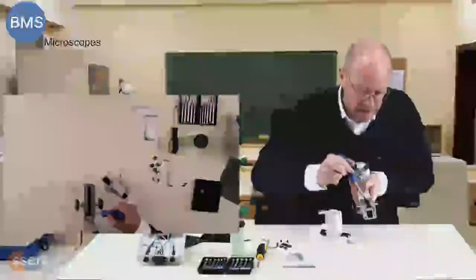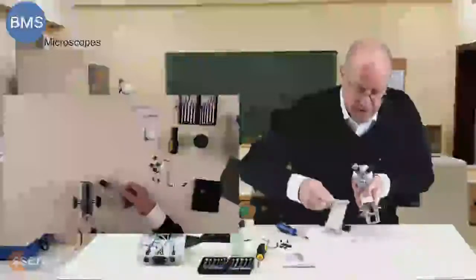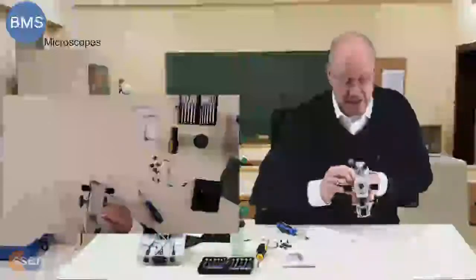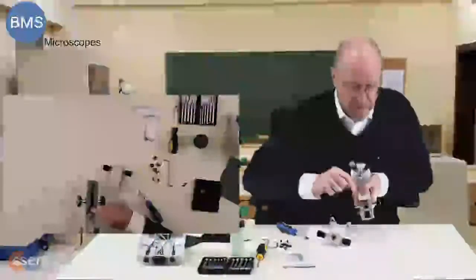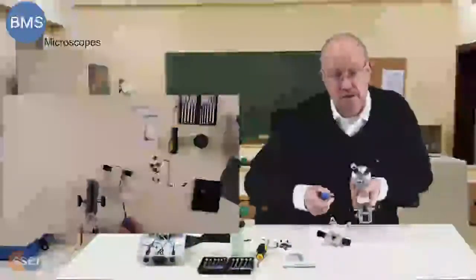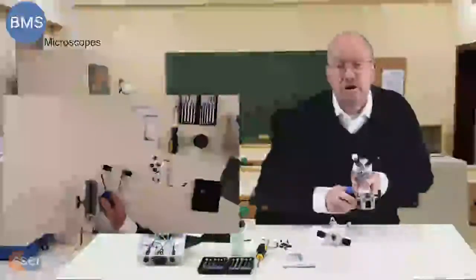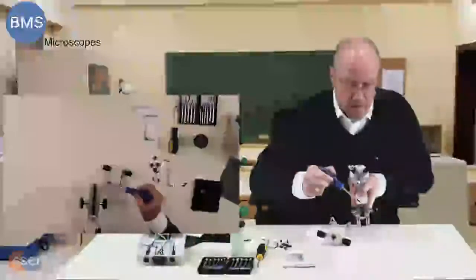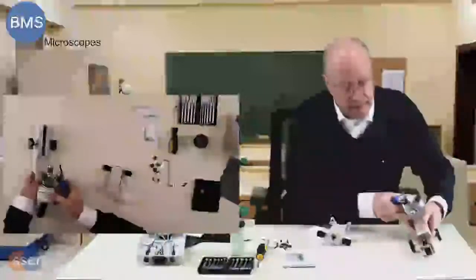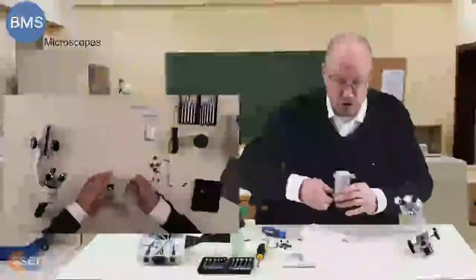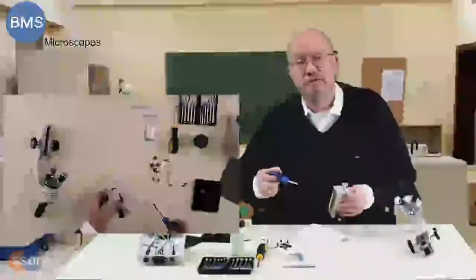And in here you will see also the slide protection. That's this screw here. You can see the moment that this comes up too high, the stage comes up too close to the objectives. This little screw here makes sure that that movement is stopped and you can't go further, and therefore the slide is protected and your objectives are protected, of course. We're not going to touch the real moving parts. The only thing we need to do is put new grease on here and new grease inside the fine focusing.